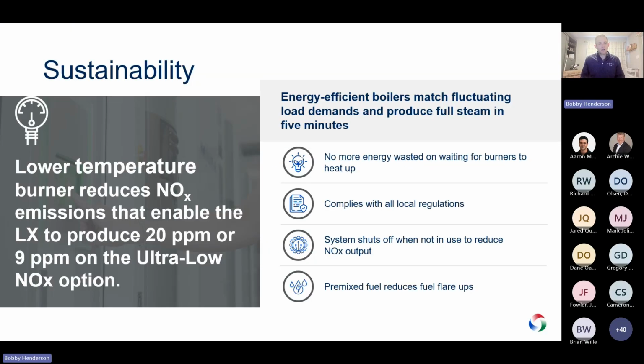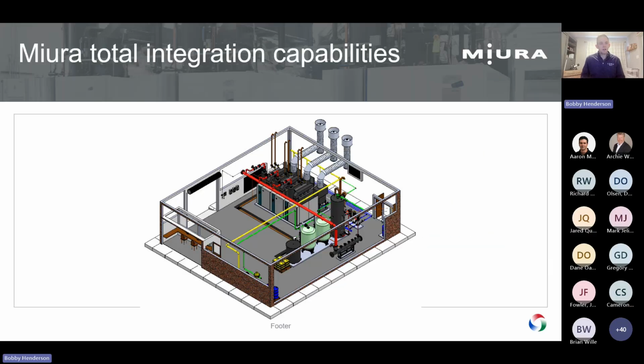And low NOx, we didn't get to low NOx. All these boilers are standard at less than 20 parts per million on natural gas. They also have an option for 9 parts per million, their ultra low NOx option. On certain models now, they even have less than 5 parts per million NOx available. I believe that's on their 300 horsepower model. That's really for the California and Chinese markets. But if you have an ultra low NOx application that you need, definitely give us a call. We can talk to you about it.